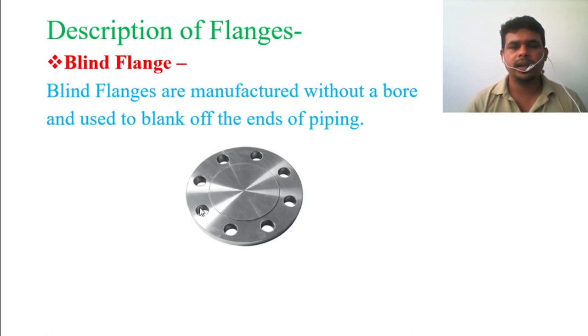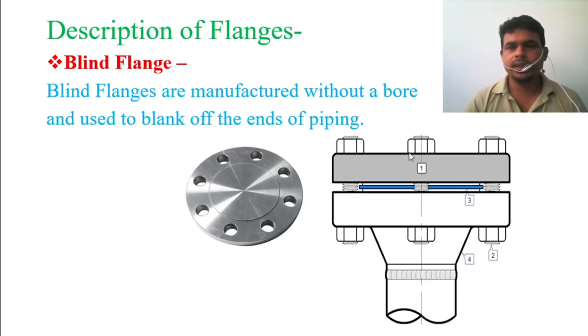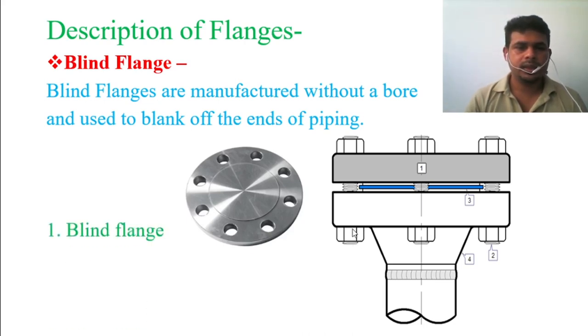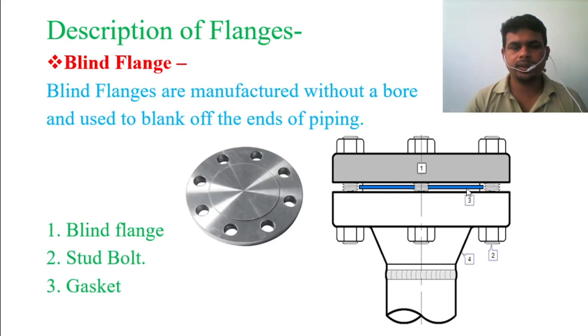If you need to blind a pipeline, or if you want to perform testing on a pipeline, you need to blind both ends or multiple locations before testing can be done. This type of flange is used for that blinding purpose. In the figure, number one is the blind flange. To use it, you need two flanges — the blind flange and a pipe flange. You also need a gasket in between to prevent leaks, and you use stud bolts or hexagonal bolts with nuts. Number two is the stud bolt, number three is the gasket, and number four is the other flange.